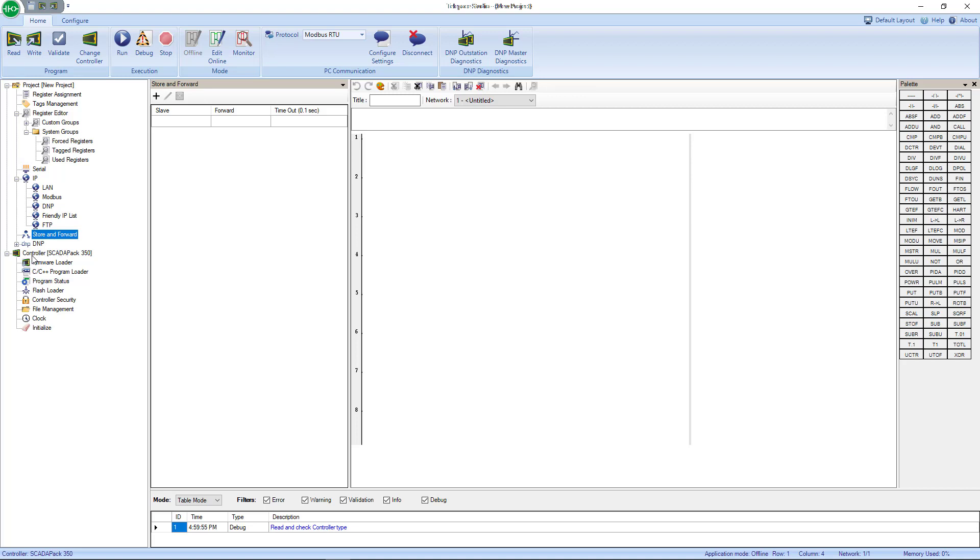Then we move into the actual Controller Hardware, which we currently have a SCADAPack 350 selected. You could change the firmware here, load a C program to the SCADAPack, check the program status, use the Flash Loader. The Controller Security is listed down here. This is really important because the Skater Packs are locked coming out of the factory now, so you have to go in here and disable that lock. As well as there's File Management. This is where you could write your configuration file to the SCADAPack so you have it later. You have your Clock—you could set it all up here—and then you have Initialize to initialize your SCADAPack.